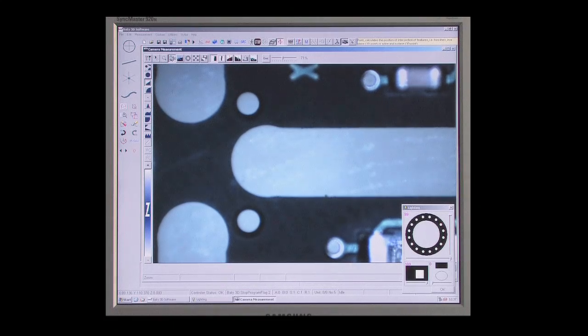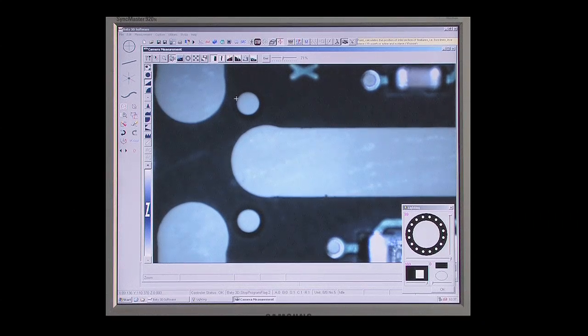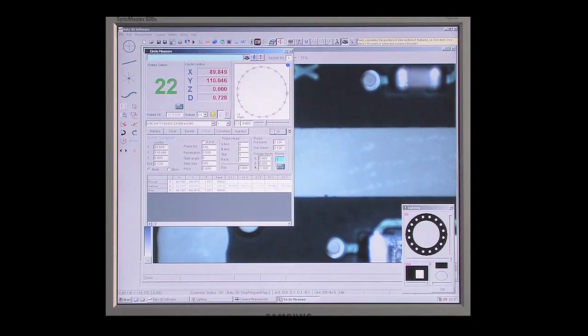Now we can measure. Using the video edge detection tools provided, we can quickly measure circles, lines, arcs, and points around the component. In each case, Fusion is finding the edge of the feature to be measured, so repeatability from one user to the next is assured.